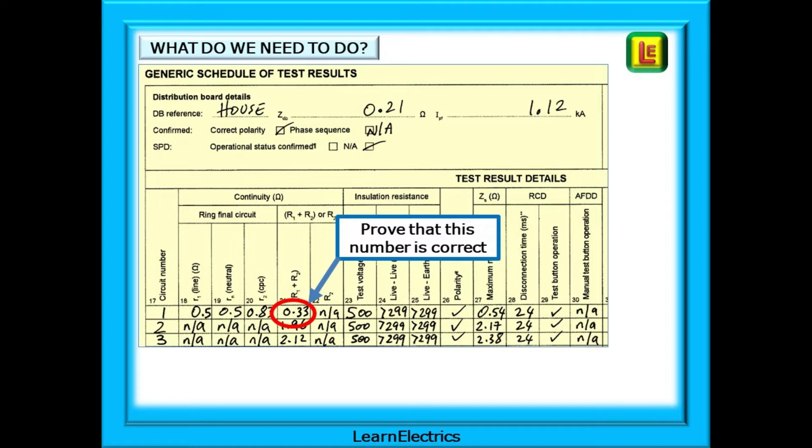What is it that we need to do? We want to prove that this number, 0.33 ohms, is correct for the values that we've recorded for the line, neutral and CPC end-to-end resistances. Many of us would call the CPC the Earth, but in an assessment, don't do this.